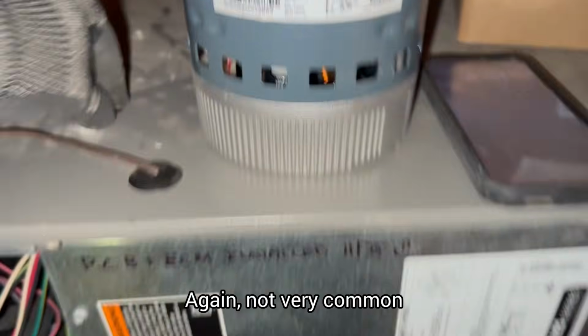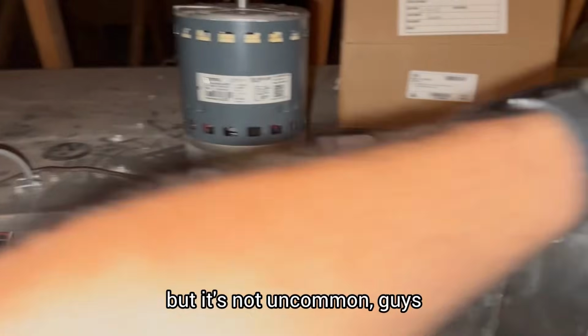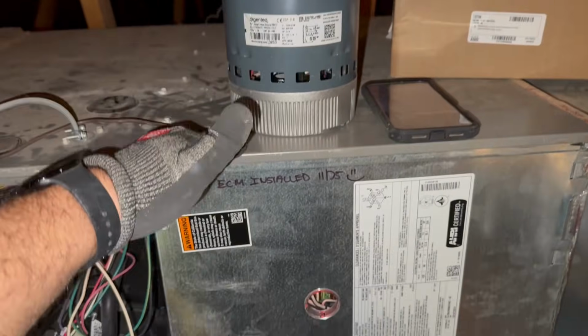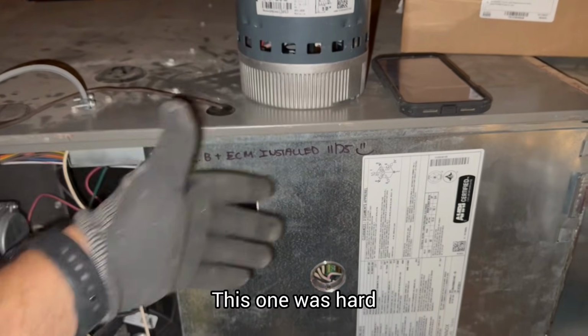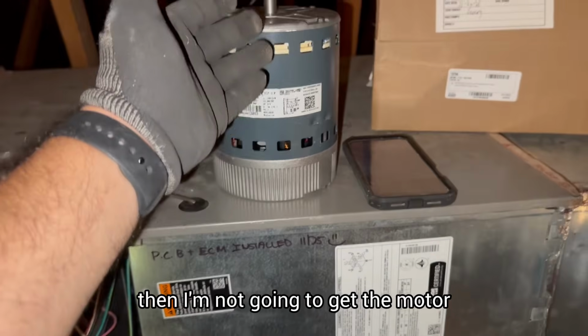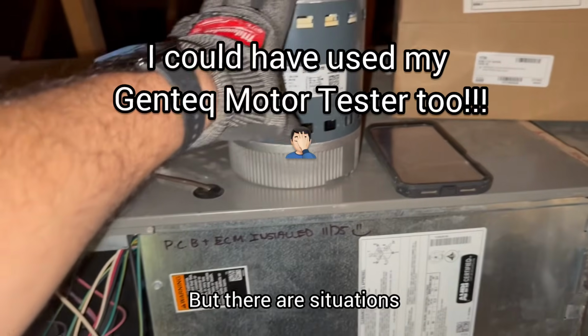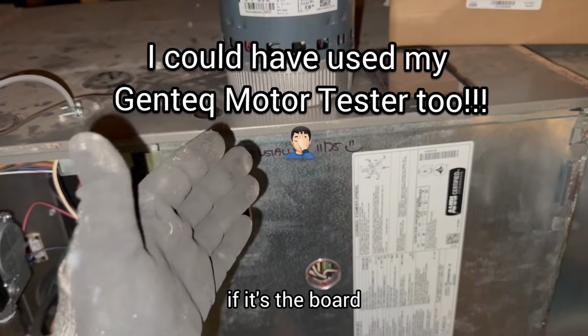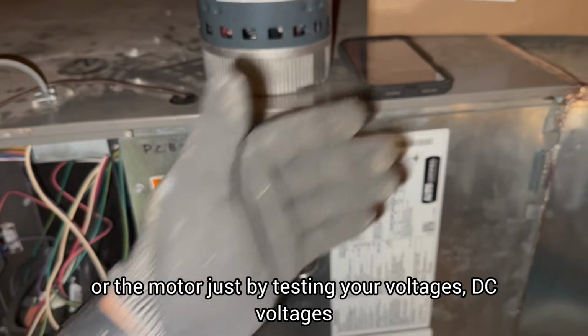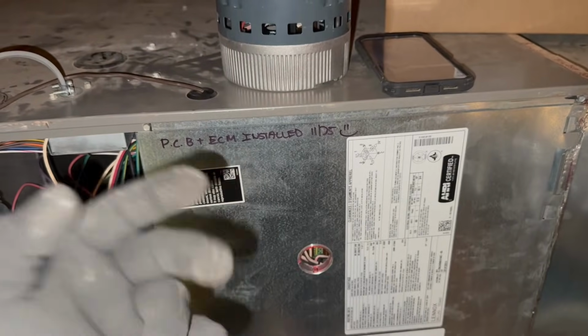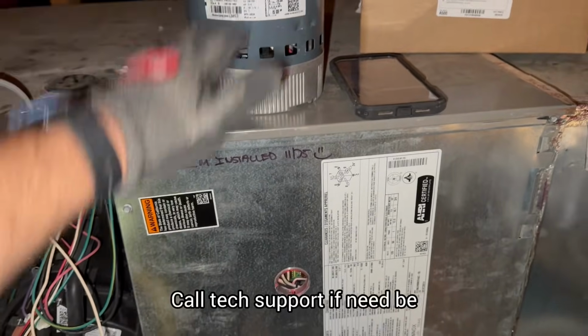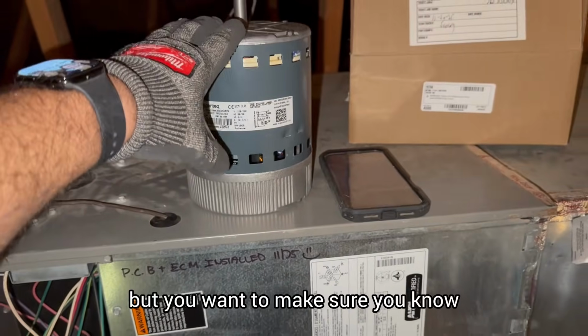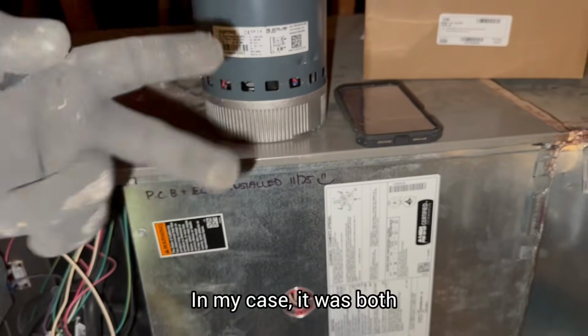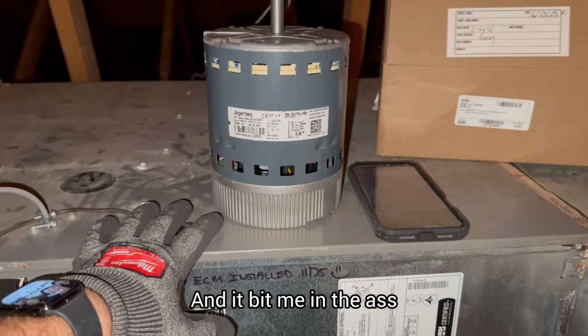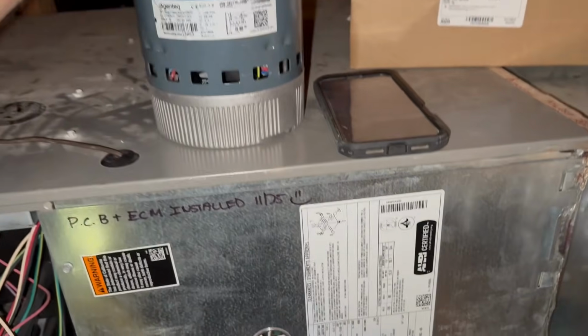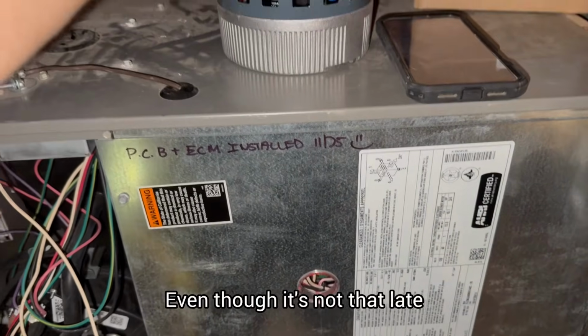Again, not very common, but not uncommon, guys. Make sure you're doing your troubleshooting. This one was hard because if I didn't have the voltage, then I'm not going to get the motor if I don't have the voltage. But there are situations where you can differentiate if it's the board or the motor just by testing your voltages, DC voltages, all your outputs and everything. Call tech support if need be, but you want to make sure you know which one is which. In my case, it was both, and it bit me in the ass, and now I'm working till 5 o'clock, even though it's not that late.